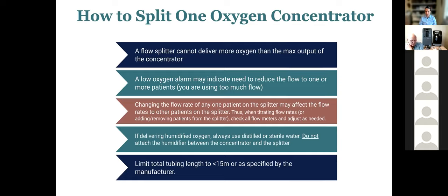Again, with humidification, always use sterile and distilled water, and make sure that you have the humidifier downstream from your check valve and from the flow meters to avoid getting moisture into the flow meters. And then limit your tubing length. If you use too much tubing, the resistance can cause some issues potentially.